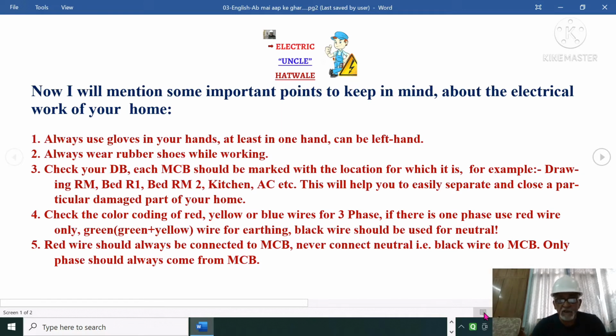Number 4, check the color coding of phase. It should be red, yellow, or blue wires. For three phase, red, yellow, blue. If there is one phase, use red wire only. Green plus yellow wire for earthing. Black wire should be used for neutral. Always follow the color code in electrical wires, so you will not get confused. Just by the color, you will be alert. If it is red, be alert.